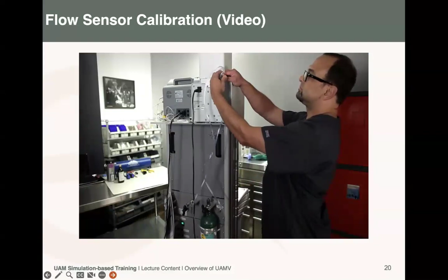When complete, press Exit. If the calibration fails, perform the procedure again from the beginning. If it fails again, you must perform a pressure transducer zero offset calibration, followed by the flow sensor calibration. If it fails again, replace the flow sensor with a new one. If a new sensor fails the calibration, please contact Gradian for service. After calibration, reconnect the flow sensor to the patient circuit Y piece and place a clean patient bacteria filter ready for the next case. Reconnect the ventilator drive hose between the bellows 17mm taper and the UAM anesthesia machine ventilator connector.